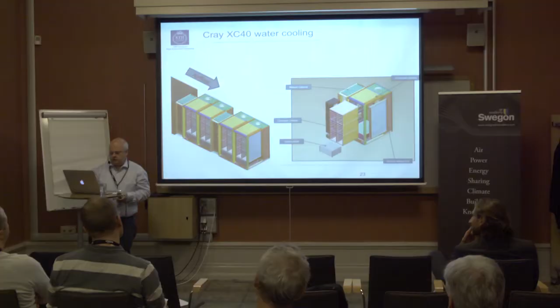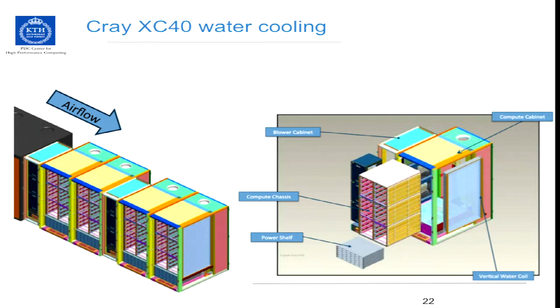You can see it in this slide. Air comes in through a row of racks — we have 9 racks total — and the air flows through all the racks. It comes in one end and comes out the other end at the same temperature it came in, because each rack has heat exchangers. So the boards are cooled by air, which is warmed up by the CPUs and then cooled down in the heat exchangers. Very neat, but in principle it's the same as those back doors or cool doors on computers — it's the same principle, just a mixed kind of hybrid cooling.